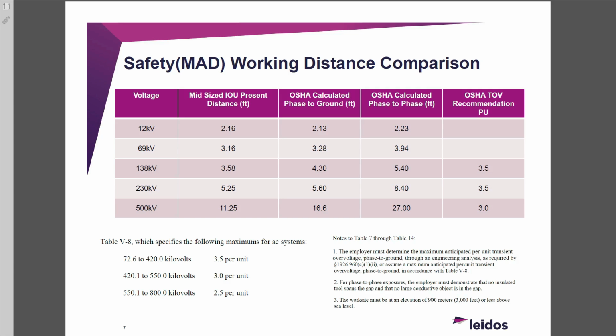But this is huge because we have a lot of clients with 500 kV lines. Now he's saying phase to ground, you're at 16 feet minimum approach, as opposed to the 11 feet his people are working on. When I do walk downs, I'm a lot closer than that -- a lot of times when I walk under a big power transformer, you don't really think about it. Our client measured the bushing to the control panel, and I can climb up on the pad and that's only 8 or 9 feet. So now they're like, well, what are we supposed to do?